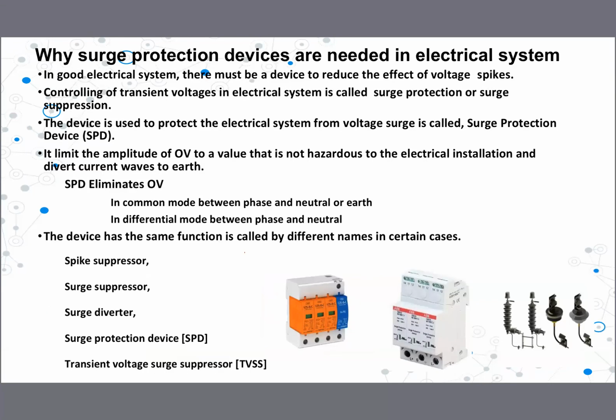Let's move on. Let's try to understand why we need a surge protection device in our electrical system, right? In a good electrical system, there must be such a device. Now, you know that if there is an overcurrent in the system, we have overcurrent protecting devices, MCB, MCCBs. If there is a short circuit, we again have a circuit breaker, MCB or MCCB, ACB, to cut off the short circuit. Then if there is earth leakage or earth fault, there are protection devices to cut off. In the same way, we need a protection device to minimize or reduce or cut off the transient voltages, right?